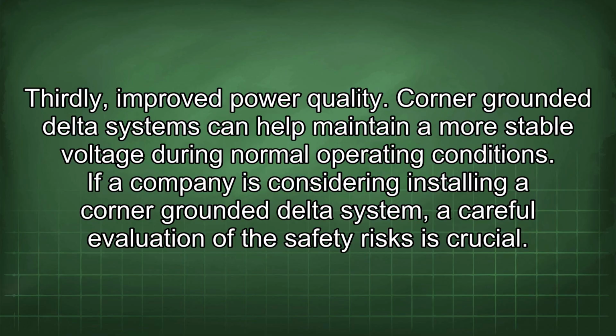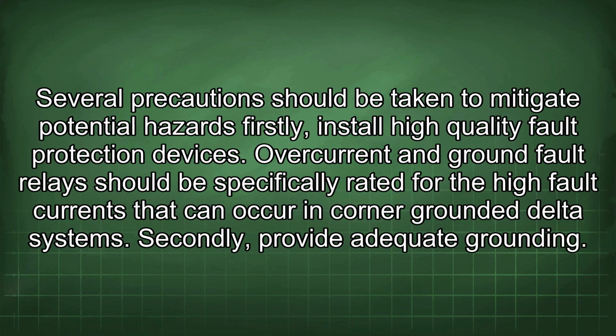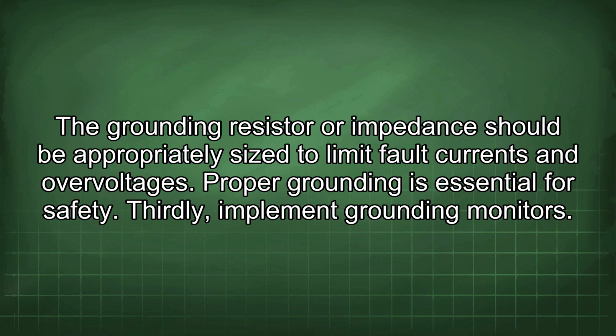If a company is considering installing a corner-grounded delta system, a careful evaluation of the safety risks is crucial. Several precautions should be taken to mitigate potential hazards. Firstly, install high-quality fault protection devices. Overcurrent and ground fault relays should be specifically rated for the high fault currents that can occur in corner-grounded delta systems. Secondly, provide adequate grounding. The grounding resistor or impedance should be appropriately sized to limit fault currents and overvoltages. Proper grounding is essential for safety.